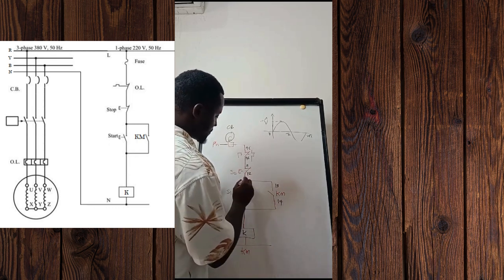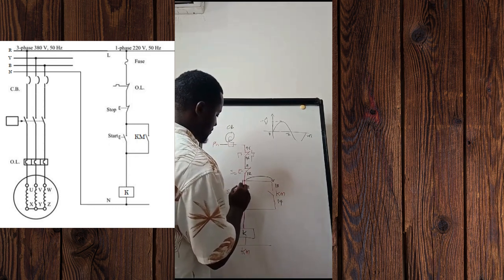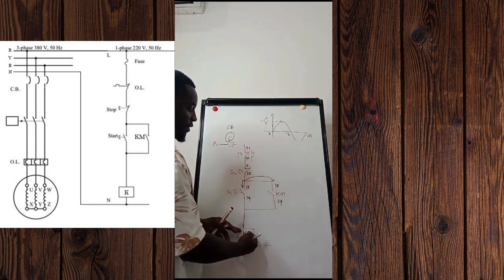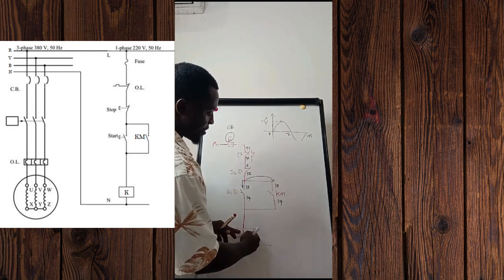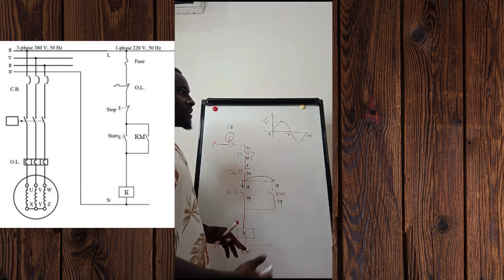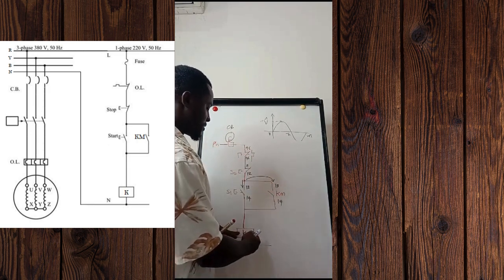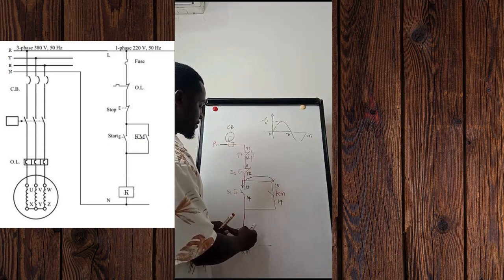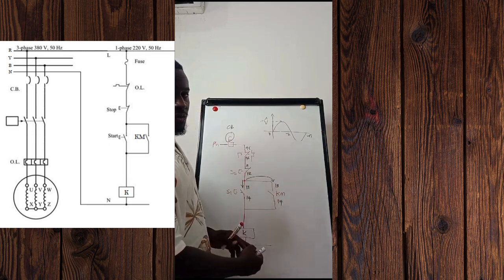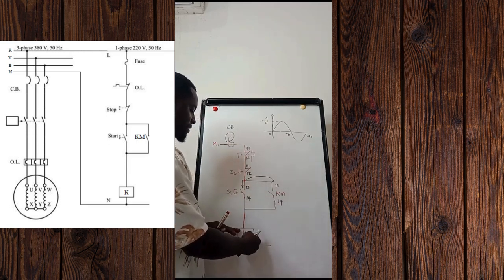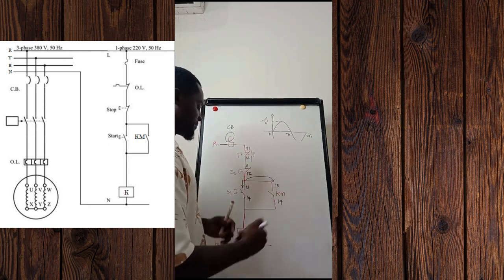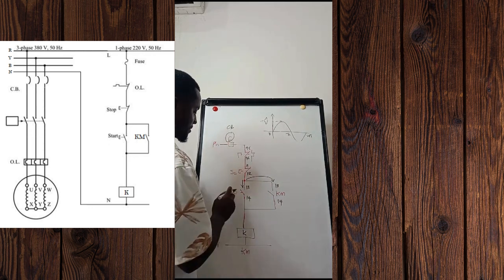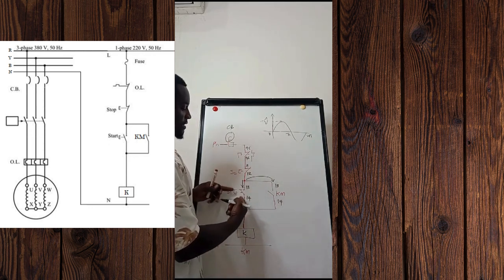At the same time, current will also move and get to the auxiliary contact level. For us to enable current to flow to the coil so that it will be energized with sufficient current and the correct voltage — you must make sure you fit the coil of the contactor with the desired voltage rating, as too much voltage could damage the coil and too little voltage means the coil may not function. Once you press the push button, it closes and current moves directly to the coil.